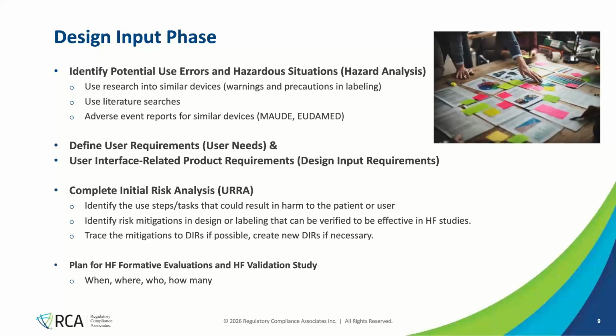Do you want to add warnings to your labeling? Do you want to provide training materials? Or do you want to design the device to eliminate something? This can all be captured in a URRA. It's a good rule of thumb to trace your mitigations to a design input requirement, because design input requirements all get verified. They don't get forgotten or left off the bottom. So if you can trace it to a DIR or make a new DIR for any new requirements you have for mitigations, if say you identify a mitigation that you're going to add a warning or add a sticker to the front of the device, make a design input requirement for that sticker.